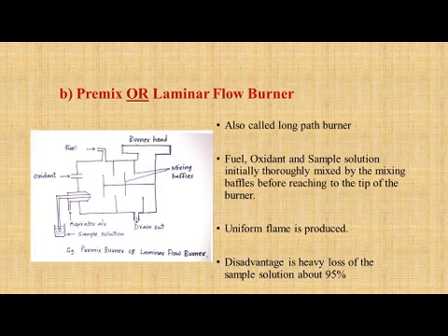That is the beauty of this burner, but it has some disadvantages, and the main disadvantage is that a heavy loss of sample solution is observed. The bigger drops are totally drained out. Nearly 95% of the sample is lost during this analysis. But this burner has good atomization efficiency. The flame we get here is non-turbulent, and we will get good results by using this premix or laminar flow burner.